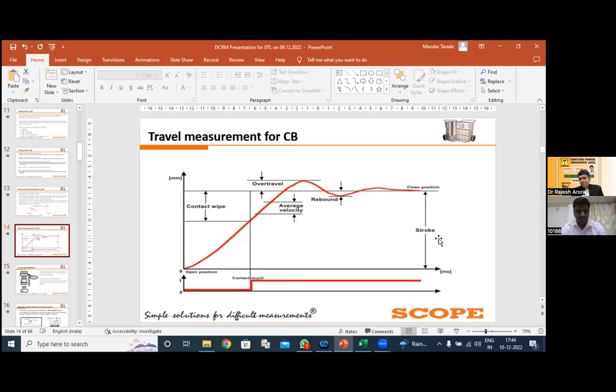Here we are applying 5 volts from any instrument, or 5 to 24 volts, and the transducer is basically a resistive element across which that voltage is applied. So whenever we perform the close or open operation, we get a change in the resistance value and accordingly the appropriate voltage drop. When calculating that delta, we equate the 5 volts to the electrical stroke length, and the delta to the unknown travel, and then we get the value of the unknown travel.